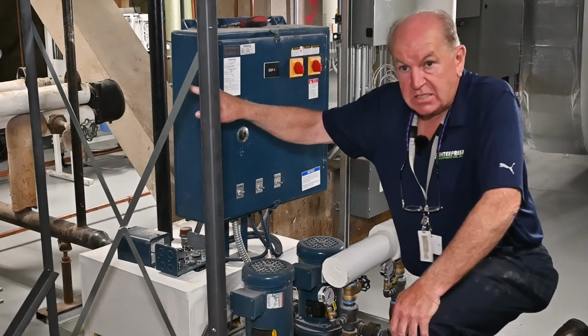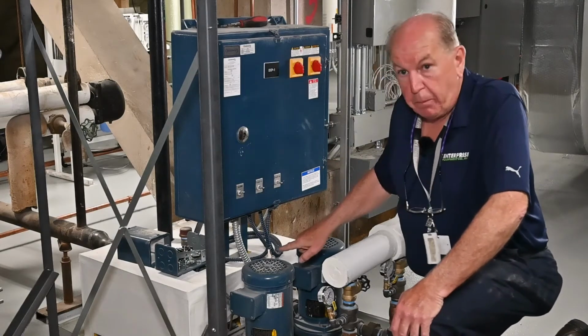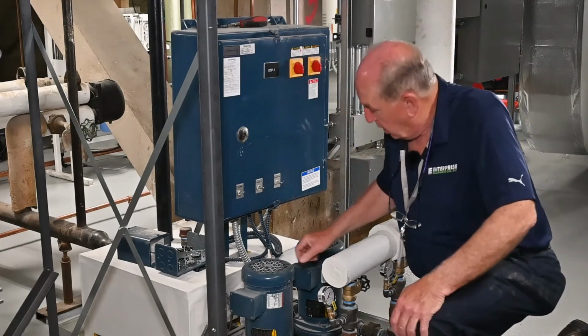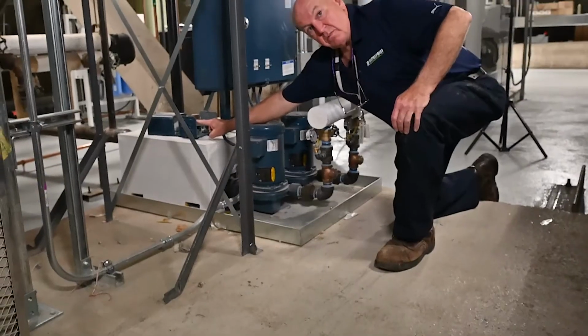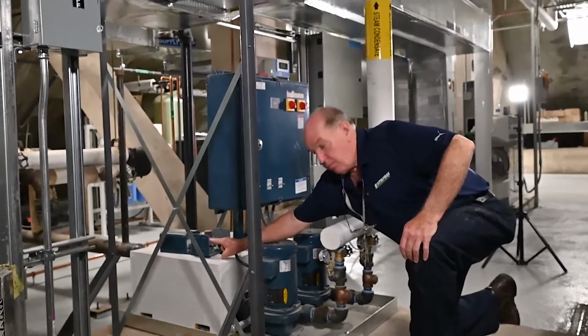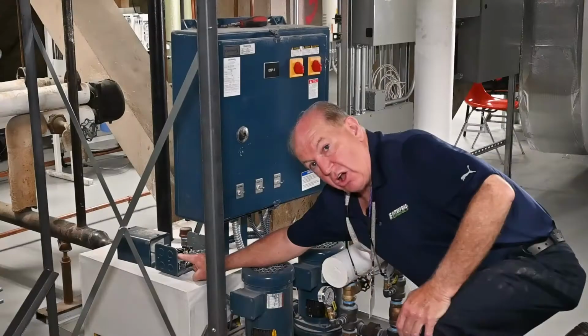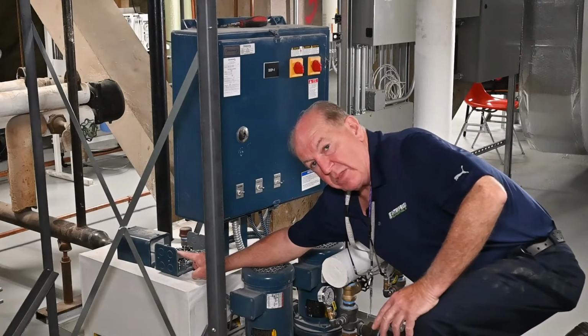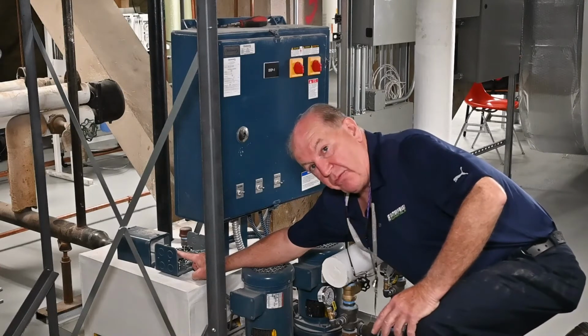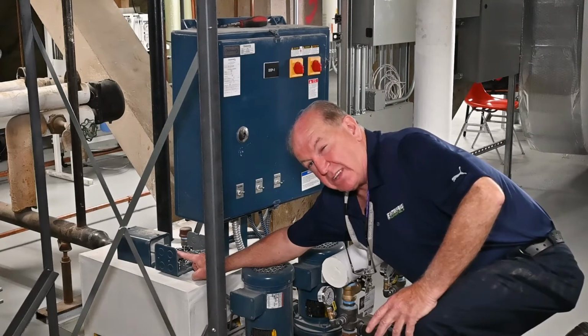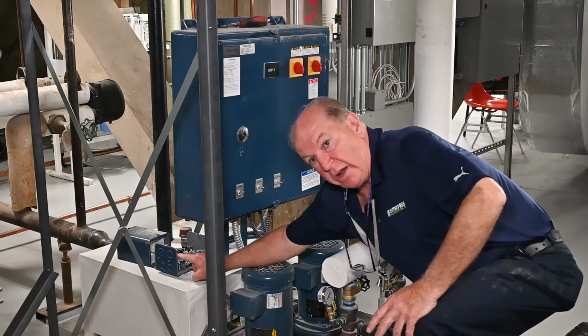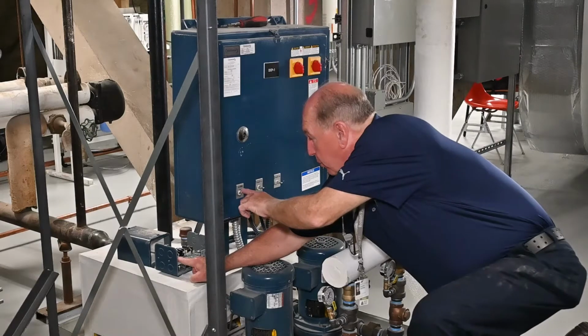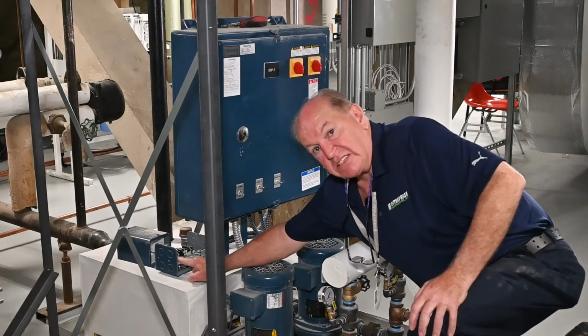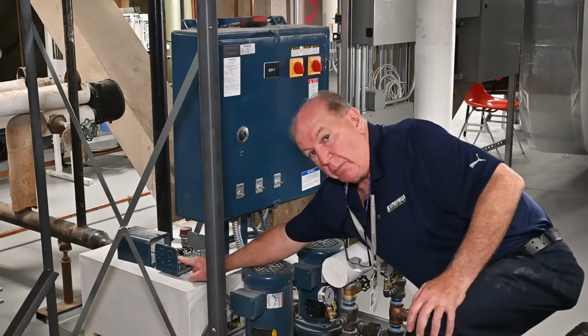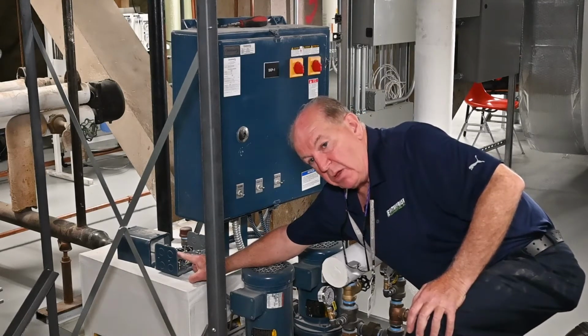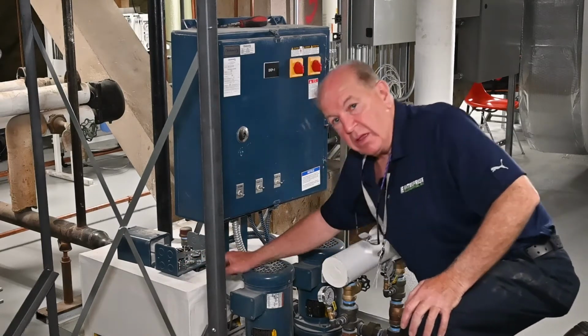So when that water condenses in the heat exchanger, it comes into this condensate pump, and this pumps it back to the system. So there's an alternating duplex float switch. Every time it turns on the opposite pump. So one time it'll be pump 1, the next time it'll be pump 2. If the water still keeps coming in and it can't keep up with one, it'll bring on both pumps and sound an alarm. That's abnormal. So if that happens, you should check the other pump. Usually that means one pump failed and the second one had to come on and pump the water.